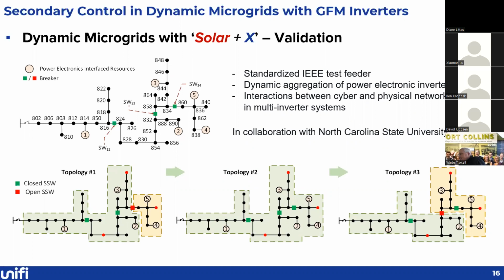We have the dynamic aggregation of grid-forming power electronics inverters, and also implement dynamic microgrids on the fly. We highlight the interactions between the communication network for information exchange, and the physical network for power sharing and frequency voltage regulation in the multi-inverter systems. The testing is also in collaboration with North Carolina State University.